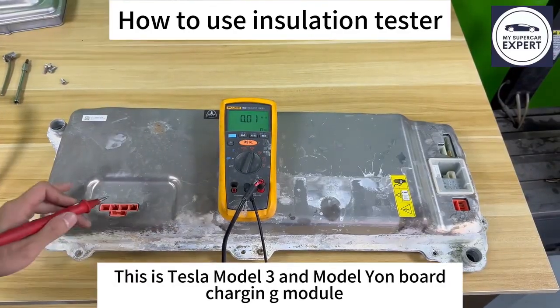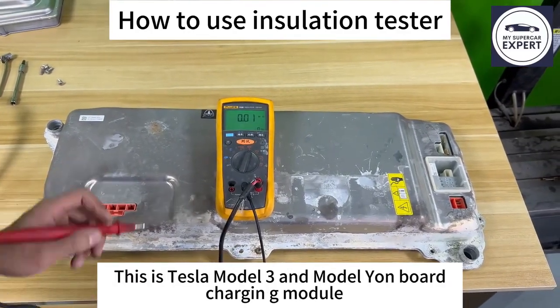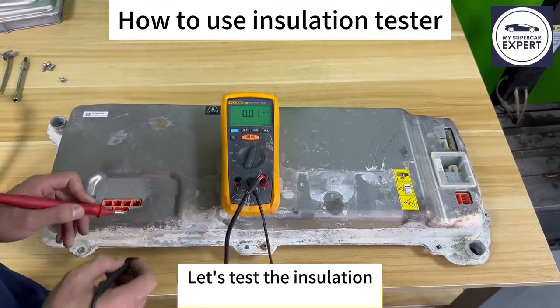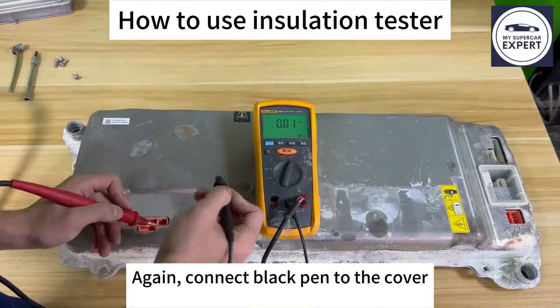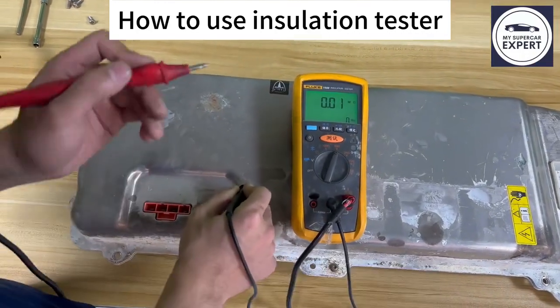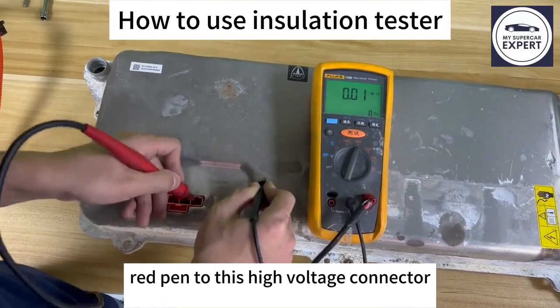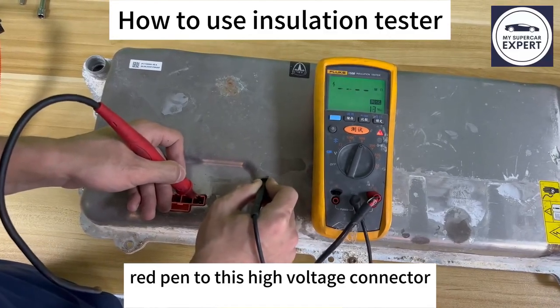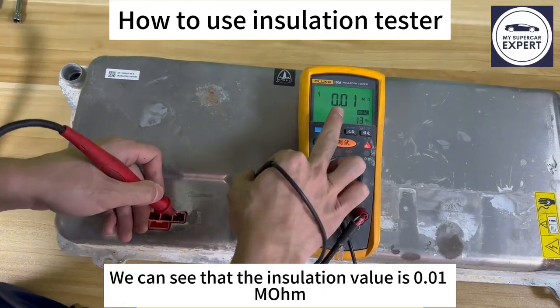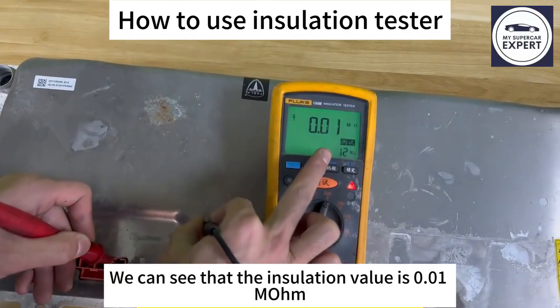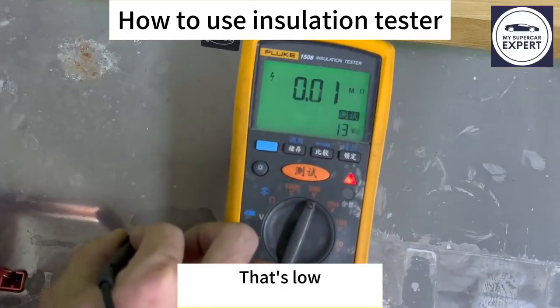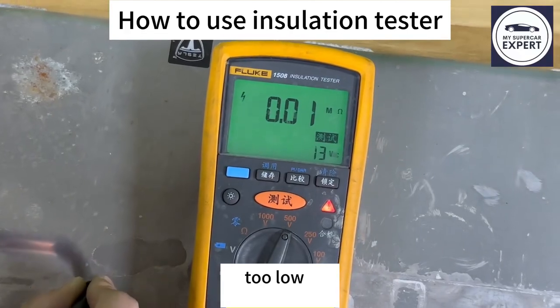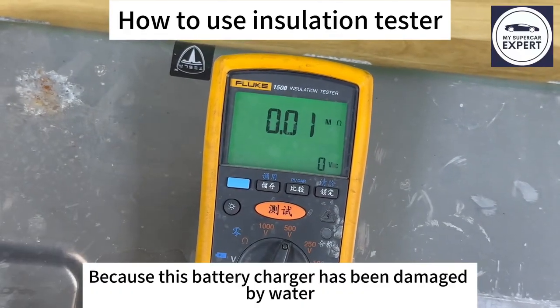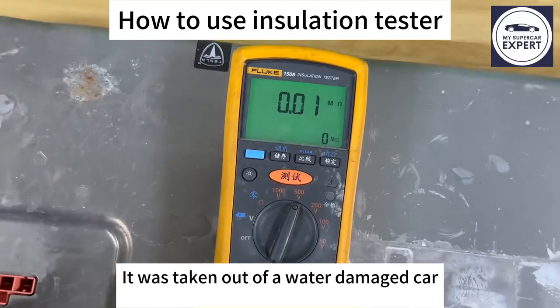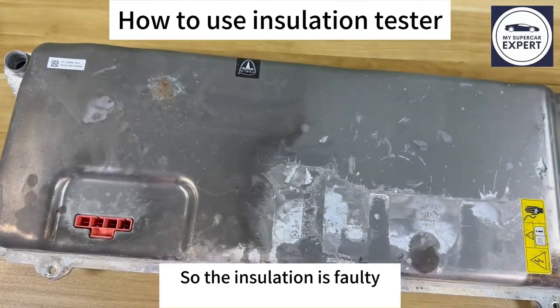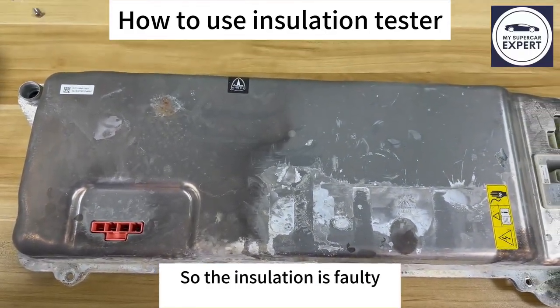This is a Tesla Model 3 and Model Y onboard charging module. It also includes the DC-DC. Let's test the insulation. Again, connect the black pen to the cover and the red pen to this high voltage connector. We can see that the insulation value is 0.01 megohms. That's low. Too low. Because this battery charger has been damaged by water. It was taken out of a water-damaged car, so the insulation is faulty.